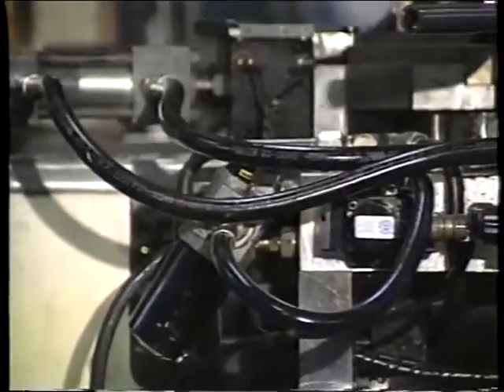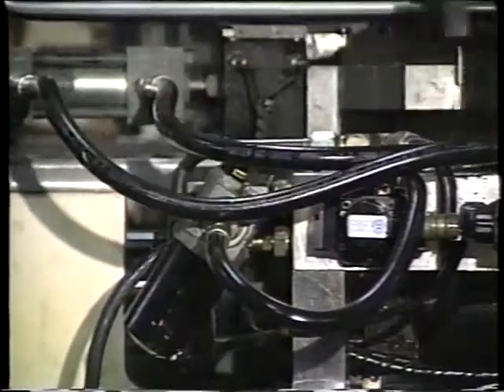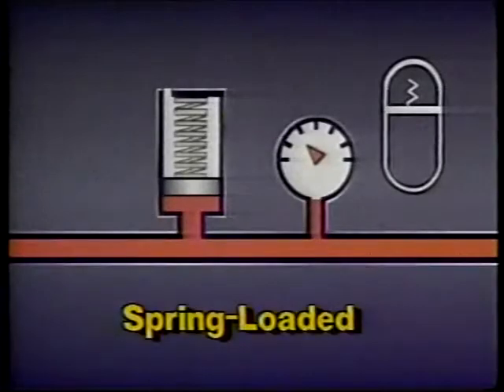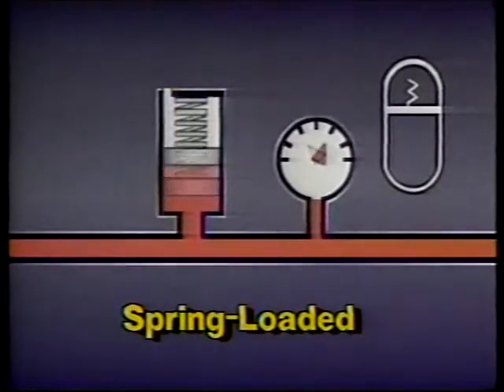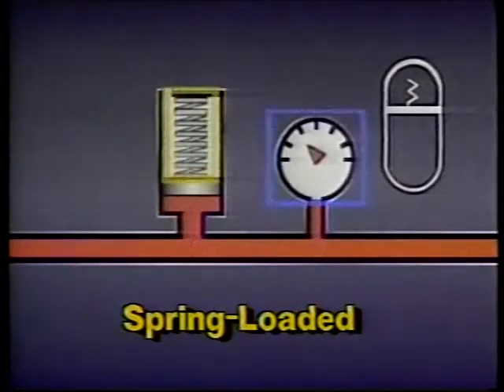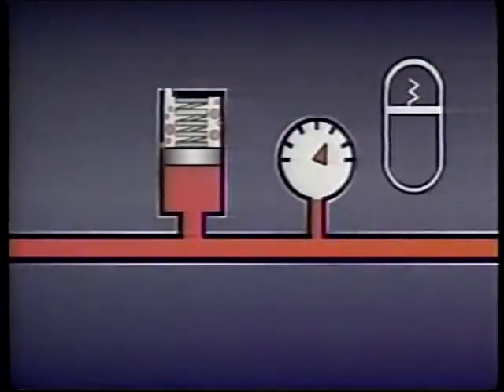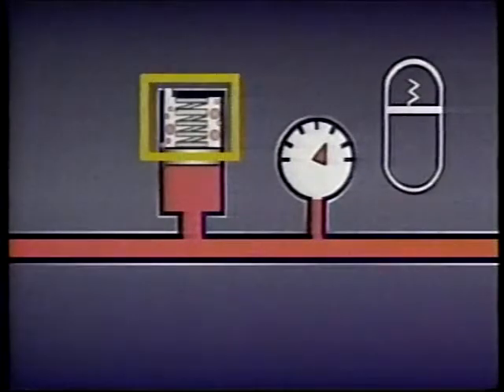However, the inertia of the weight can create shock when discharge from the accumulator is suddenly stopped. A spring-loaded accumulator has a spring that is compressed as fluid is pumped into the accumulator. The fluid pressure increases as the spring is compressed. When the accumulator is discharged, the spring decompresses and fluid pressure decreases. The spring chamber on a spring-loaded accumulator is vented to prevent the buildup of fluid which may leak past the piston.